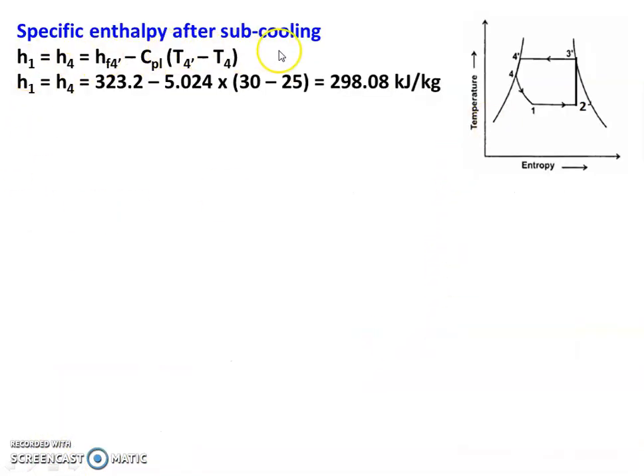And the specific enthalpy after subcooling. H1 equal to H4 equal to Hf4 dash minus Cpl into T4 dash minus T4. H4 dash is the enthalpy before expansion, which is Hf4 dash, the saturated liquid, and Cpl is the specific heat of the liquid. The second part, Cpl into T4 dash minus T4, is the enthalpy decrease due to the subcooling or undercooling.